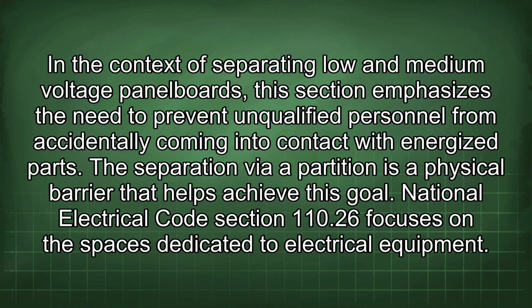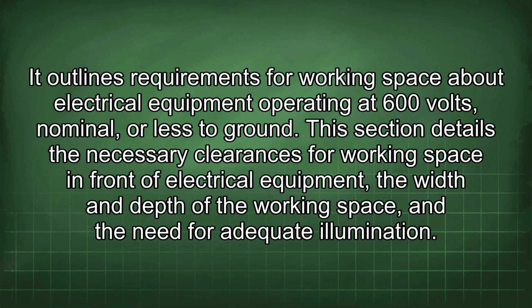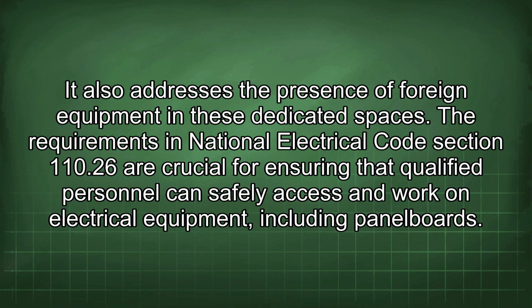National Electrical Code Section 110.26 focuses on the spaces dedicated to electrical equipment. It outlines requirements for working space about electrical equipment operating at 600 volts, nominal, or less to ground. This section details the necessary clearances for working space in front of electrical equipment, the width and depth of the working space, and the need for adequate illumination. It also addresses the presence of foreign equipment in these dedicated spaces. The requirements in National Electrical Code Section 110.26 are crucial for ensuring that qualified personnel can safely access and work on electrical equipment, including panel boards.